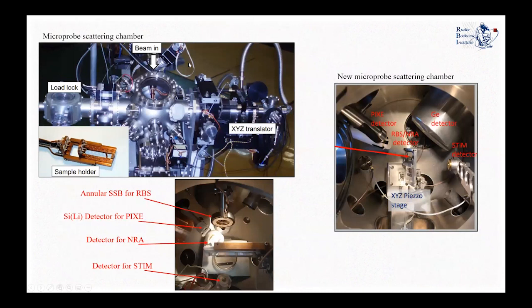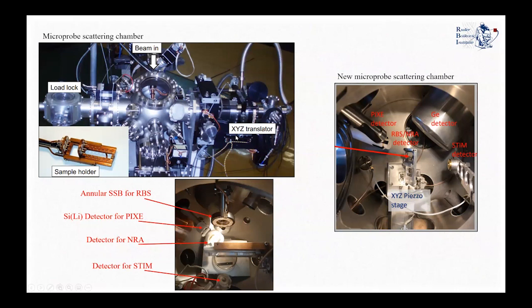The microprobe chamber looks like the image shown here. Because a microbeam can be used for many different applications — not just one kind of ion beam analytical technique or irradiation — one needs many ports to introduce many detectors. An important feature is a viewport to see the beam, because when focusing, one needs to irradiate some scintillation material and visually see the beam to adjust its size on the scintillator. There is also a load lock for easy sample loading, and motorized translators to manipulate the beam in x, y, z translation as well as rotations.